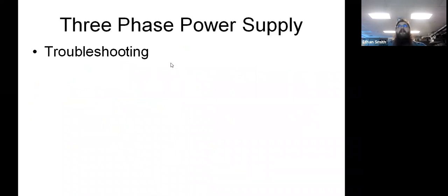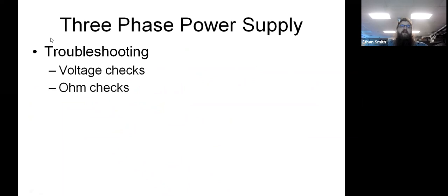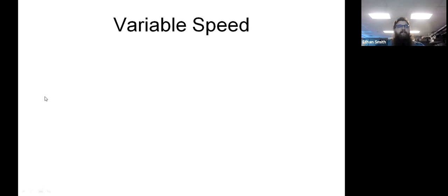Okay, so 3-phase power supplies. 3-phase power supplies have the same problems as single-phase power supplies in terms of troubleshooting. You want to do your voltage checks. Also, we need to do ohm checks a lot more with 3-phase because our 3-phase systems, especially motors, need to be balanced. Okay, so when we're dealing with a motor, we should have equal resistance on all 3 legs, and we'll show you that in just a second.